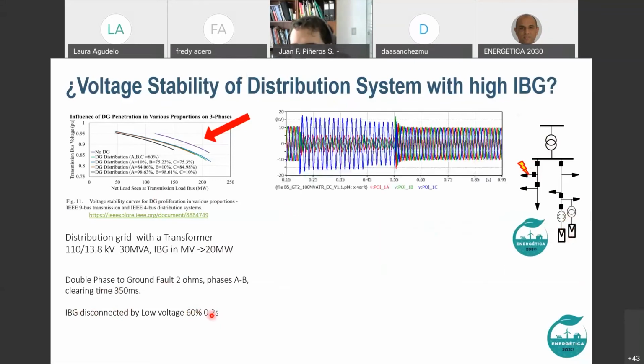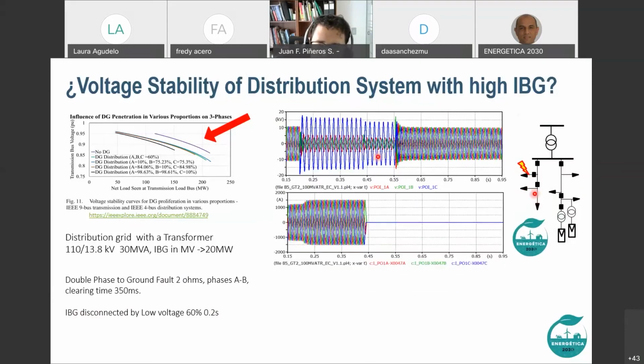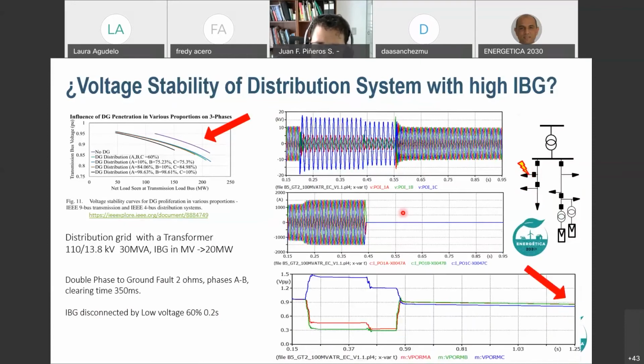And if you have in this network a load that is not only linear, and nowadays we have a lot of power electronics in all the devices, then they can operate at low voltage while trying to consume the same power. In that case, with these settings, we have a failure. We have the disconnection of the inverter-based generation 200 milliseconds after the fault, and then the tripping of this circuit part, and this is what you can have.